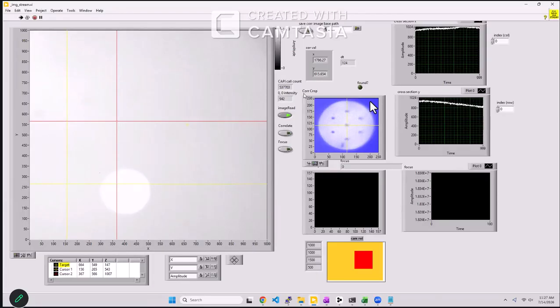You can assume that it's a Gaussian across each dimension. And then we can have a golden sensor in manufacturing that we think is the most representative of all the sensors that we're ever going to produce, right smack in the middle of all the Gaussian curves. And that puts us as close to as representative of our population as possible.